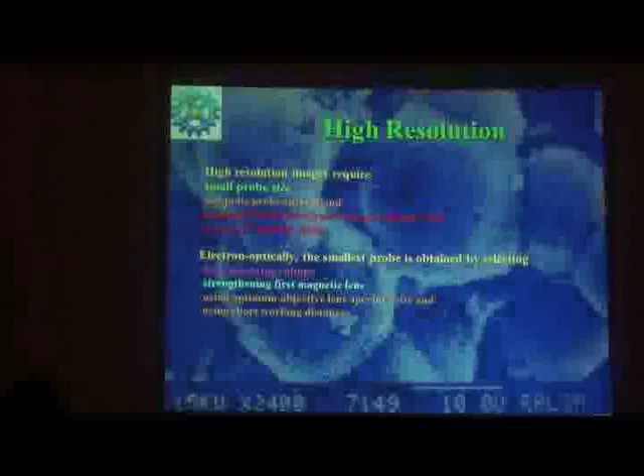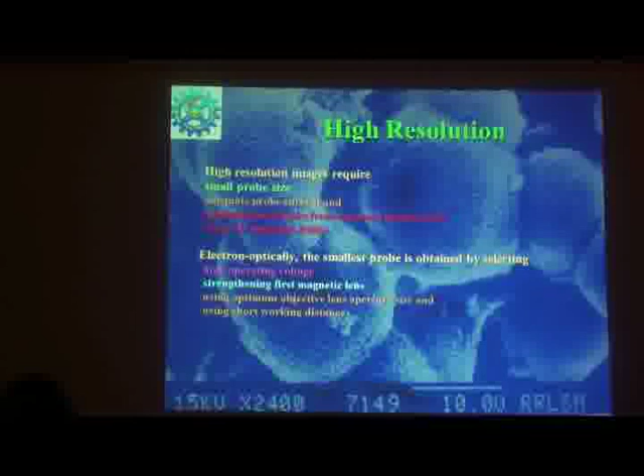High resolution depends on a small probe size, with adequate probe current and minimal interference from vibration and stray fields. When you do very high resolution work, there should not be any extra magnetic interference to the electron beam. Even opening and closing the door is not allowed. You can get a small probe size by strengthening the magnetic lenses, using an optimum objective lens aperture size, using a short working distance, and strengthening the condenser lens. These are the ways one can get very high resolution in the electron microscope.